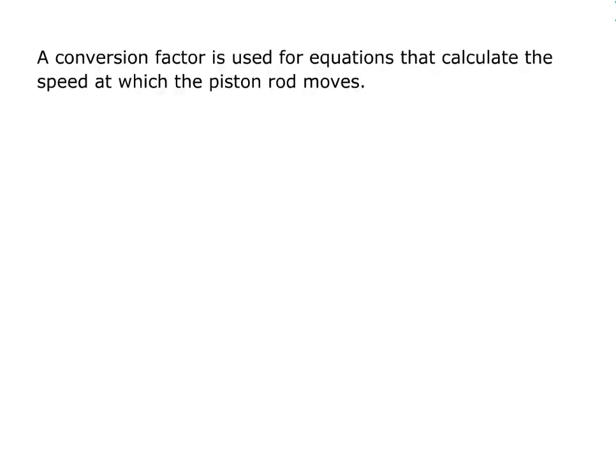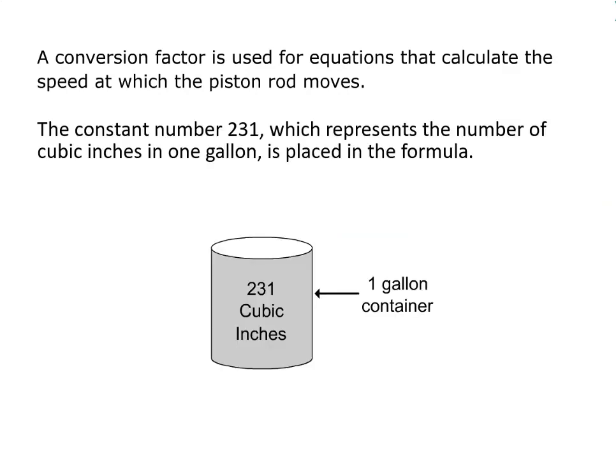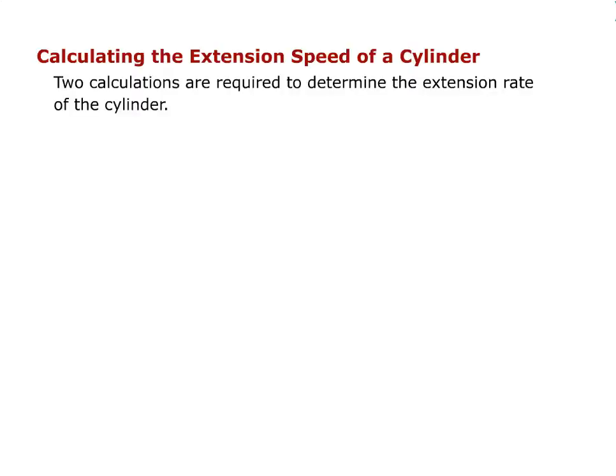A conversion factor is used for equations that calculate the speed at which the piston rod moves. The constant number 231, which represents the number of cubic inches in one gallon, is placed in the formula. Two calculations are required to determine the extension rate of the cylinder.